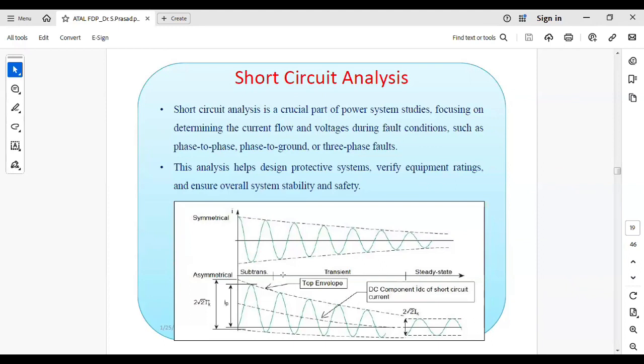And what is the fault current contributed by the grid? Suppose a short circuit happened, then what is the fault current contributed by the grid, and what is the fault current contributed by the PV plant? Those things we have to observe. Then we have to decide the rating of the circuit breaker and the rating of the CT and PT. Everything will be decided after conducting the short circuit analysis. So whenever you are going for the installation of a PV plant, the basic preliminary analyses to be done are reactive power analysis and short circuit analysis, because the short circuit analysis will decide how the grounding system will be designed, based upon the short circuit current.